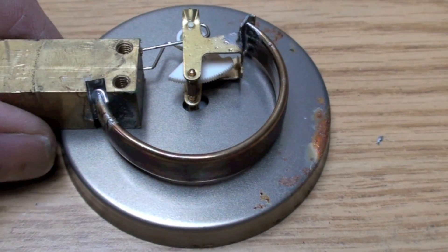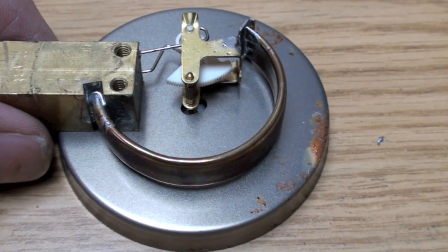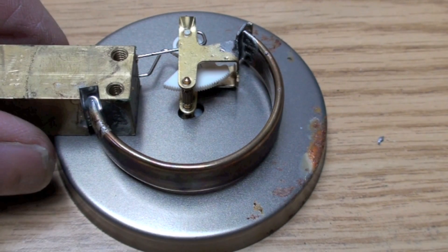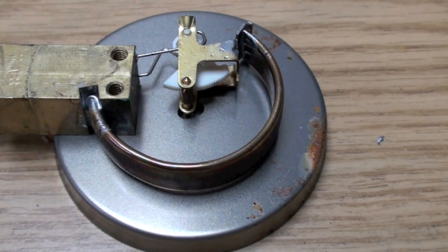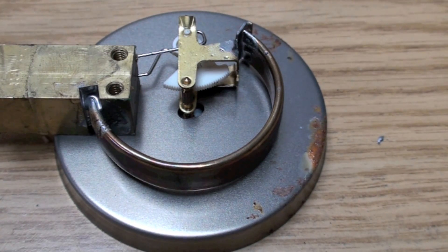Very simple device. If you over pressure these things, they do tend to kind of damage that Bourdon tube and so it may not work properly if it's been pretty massively over pressured. But they are mechanical, they do wear out, and they occasionally sometimes leak.